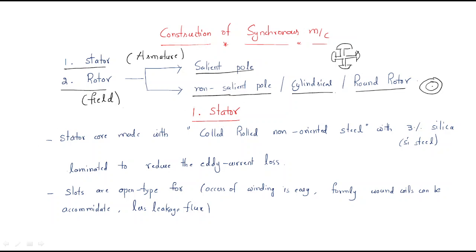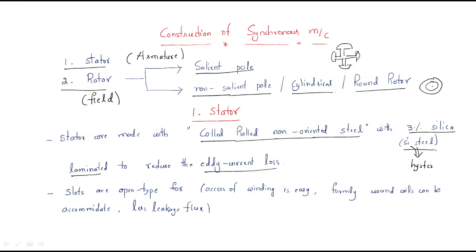First, we will discuss the stator. The stator core is made with cold rolled non-oriented steel, which is very useful to reduce hysteresis losses as well as eddy current losses. Three percent silica is added, which is why it is called silicon steel. Silica reduces hysteresis losses, and lamination is done to reduce eddy current losses.